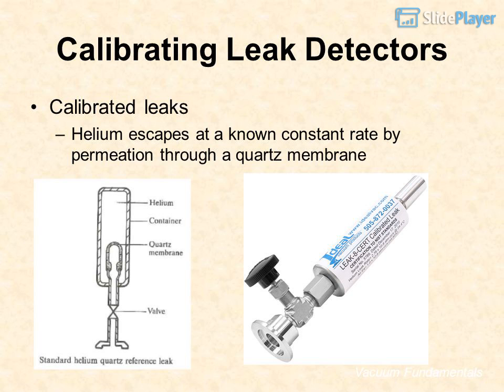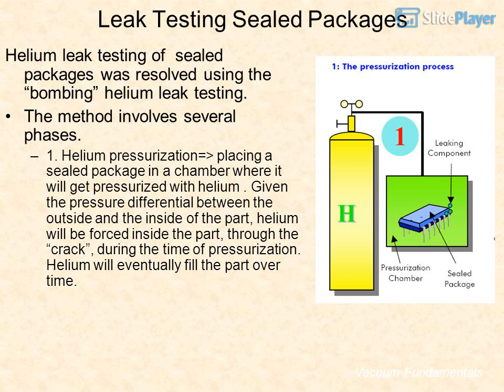Calibrating leak detectors. Calibrated leaks: helium escapes at a known constant rate by permeation through a quartz membrane. Leak testing sealed packages.